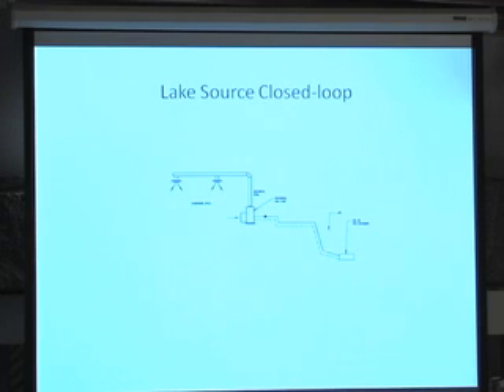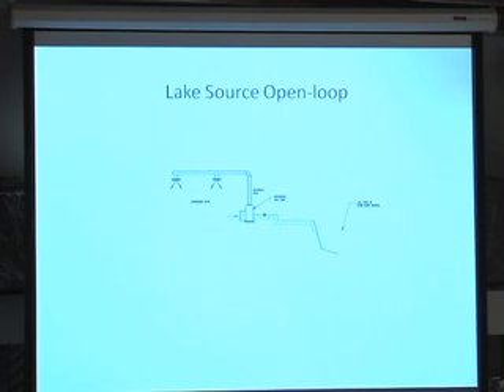This configuration is a closed loop in the sense that you're not taking the lake water to use directly, but you drop down a heat exchanger here. You pump the water in the closed loop through the heat exchanger and back to the heat pump. Another configuration is that you don't use a heat exchanger in the lake, but you take the water from the bottom of the lake and pump it through the heat pump, and then you dump it back to the surface of the lake.